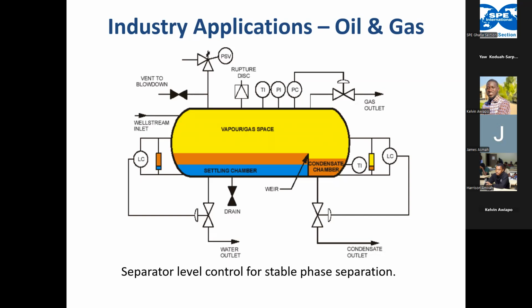And then we have another level transmitter on the right side, which is for the condensate chamber. So it also keeps the liquid in there, so that it doesn't go so high as to have condensate in the gas phase, or go so low as to have gas entering the condensate outlet. You could have a pump at the condensate side, and you wouldn't want to bring gas inside it, which can damage the pump. So that's one application of process control.